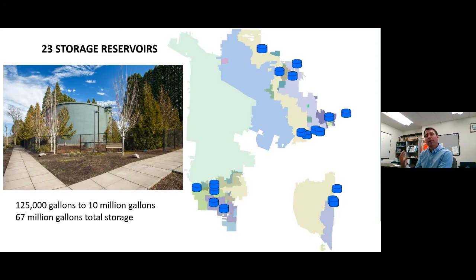We'll talk about how we manage that storage and make sure we keep it fresh, because bigger is not necessarily better when it comes to water tanks. We want to right size those so they'll meet our customer needs without having an excess of storage that can be hard to turn over and keep fresh. When we think about that chlorine residual we talked about earlier, as water ages and that residual declines, that's when we want to start using it up so we maintain that level of chlorine in there as a barrier.